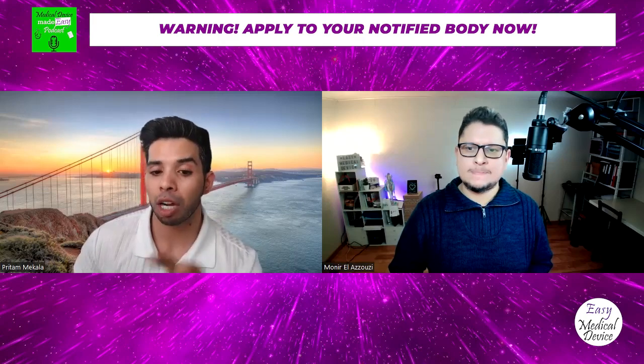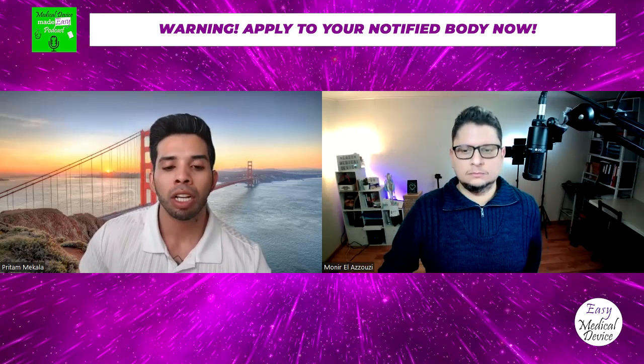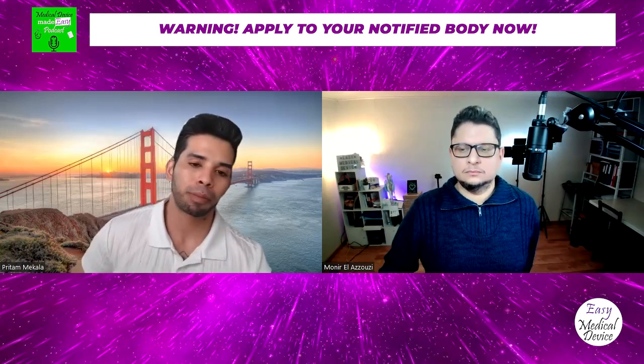So for manufacturers that are located outside the EU, it's assumed that the PRRC should be located outside the EU as well. On the other hand, if the manufacturer is located in the EU, it is also assumed that the PRRC is located within the EU. So I agree with what you said. I think that's the right answer on that topic: having an EC rep doesn't necessarily qualify you to comply with the PRRC requirement. We've seen this in the industry, an individual can have two different titles, but the job descriptions are pretty unique, and they have to understand that and lay that down for the PRRC and the EC rep. Great.